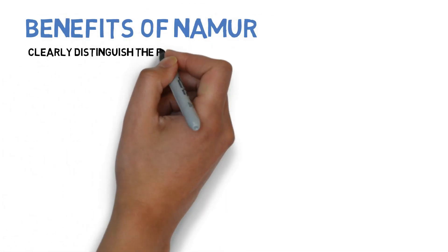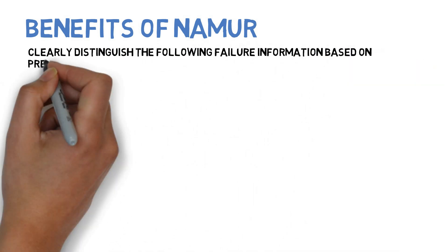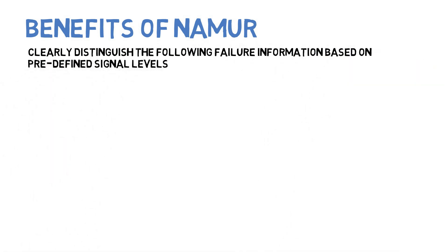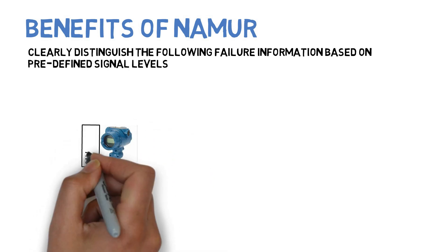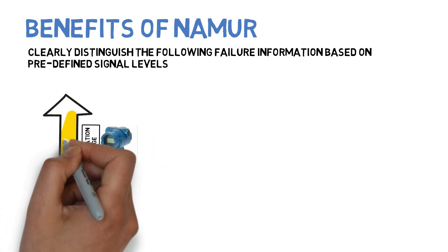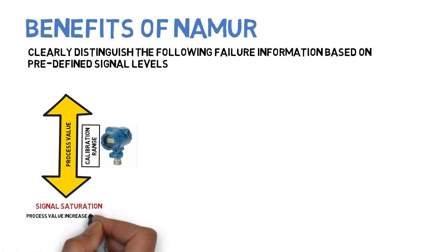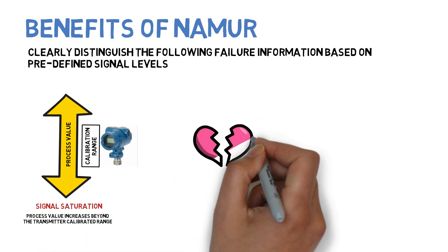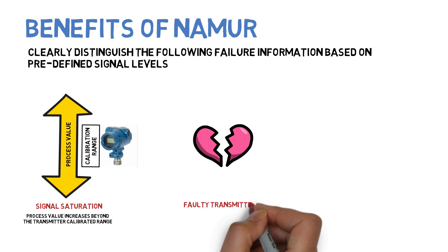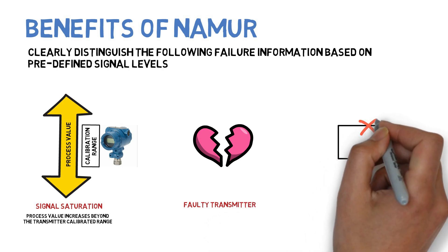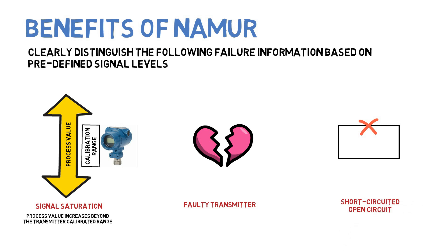The benefits of NAMUR are that we can clearly distinguish the following failure information based on predefined signal levels: when the transmitter goes into saturation due to the increase in process variable value beyond the transmitter calibrated range, and when the transmitter becomes faulty, whether the wires are short-circuited or in open circuit.